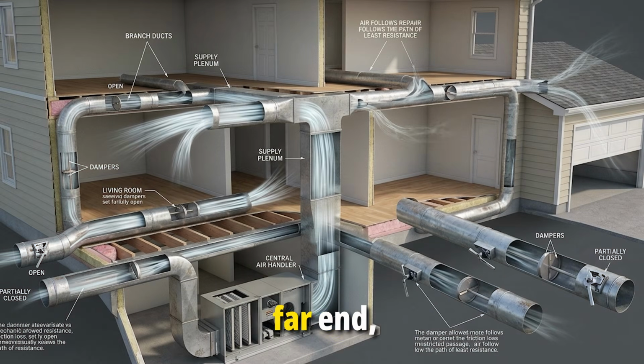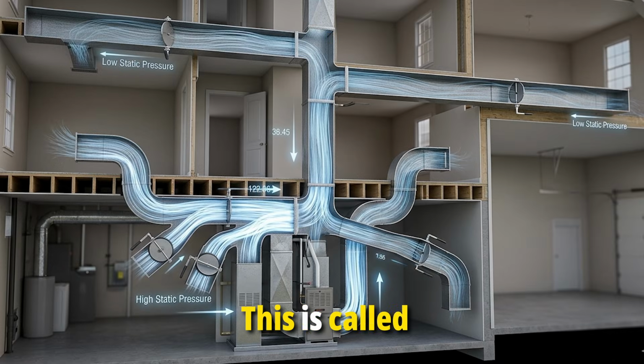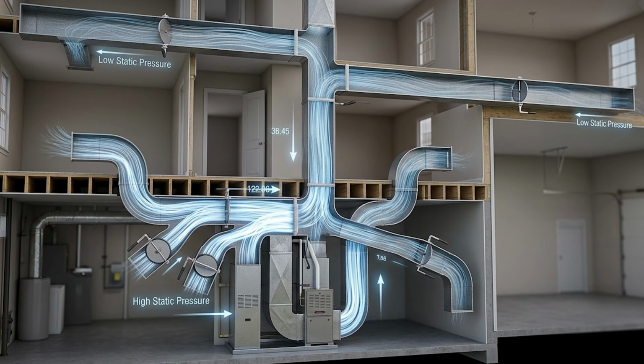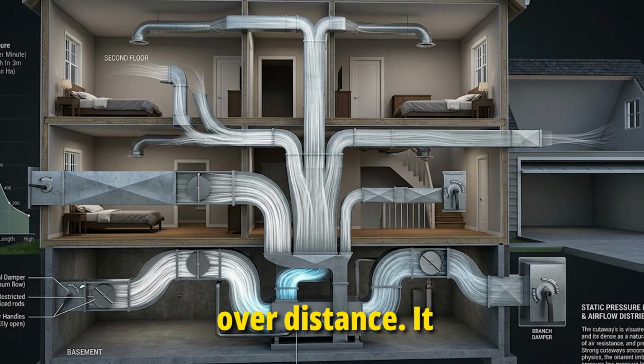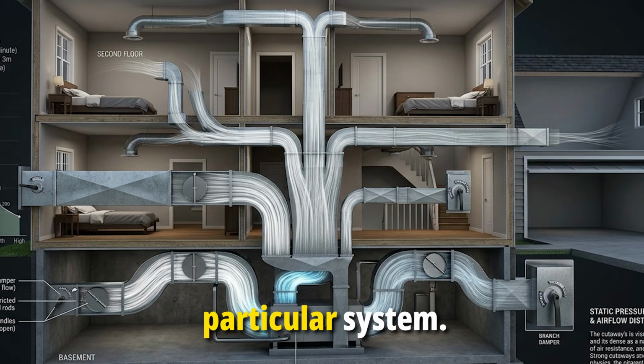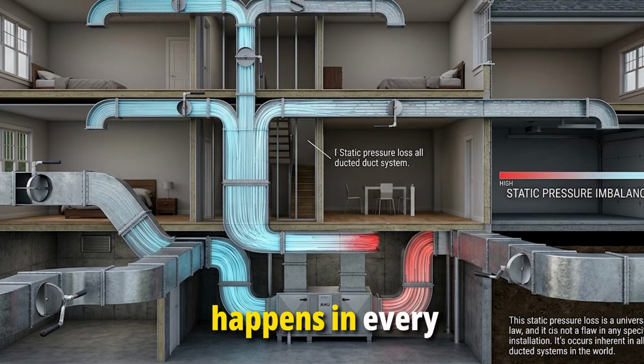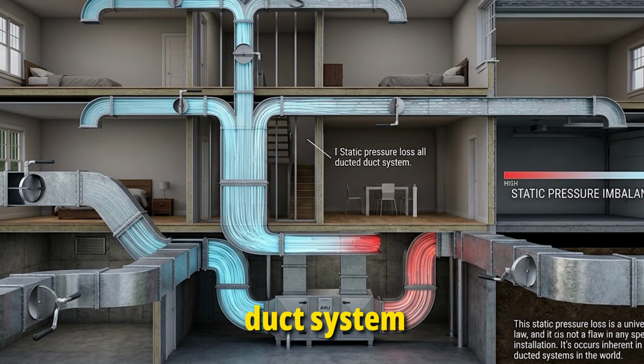The ones at the far end, the long runs, the second-floor bedrooms, the room above the garage, get what is left over. This is called static pressure imbalance. Pressure drops over distance. It is not a flaw in your particular system. It is physics. It happens in every home, in every duct system without exception.